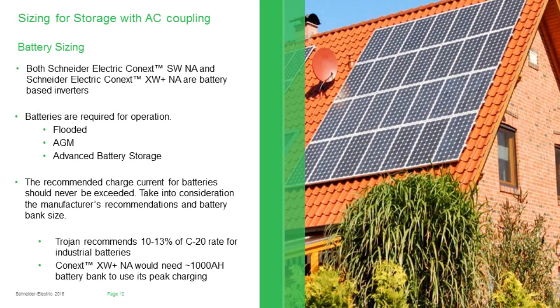So when the inverter system's in normal operation, or let's say that the grid does come back, that grid tie inverter is going to reconnect to the grid because now the XW Plus is in pass-through. But then the XW Plus is actually going to be in charge of buying power from the grid to charge the batteries. So if you put less than, say, 1,000 amp hours into that system, then you need to turn the charging rate of that inverter down. And same true for the Conext SW as well.